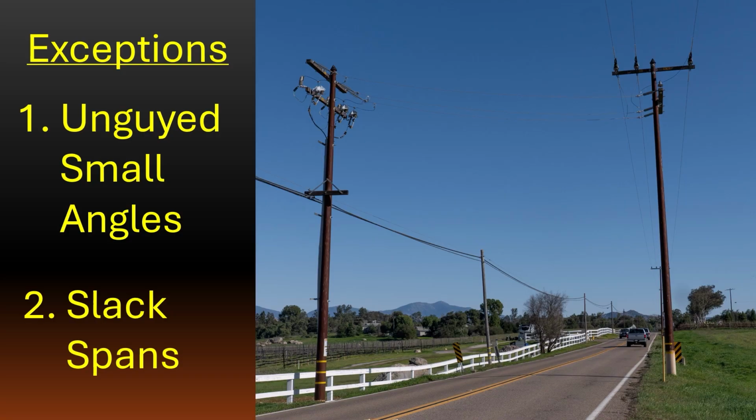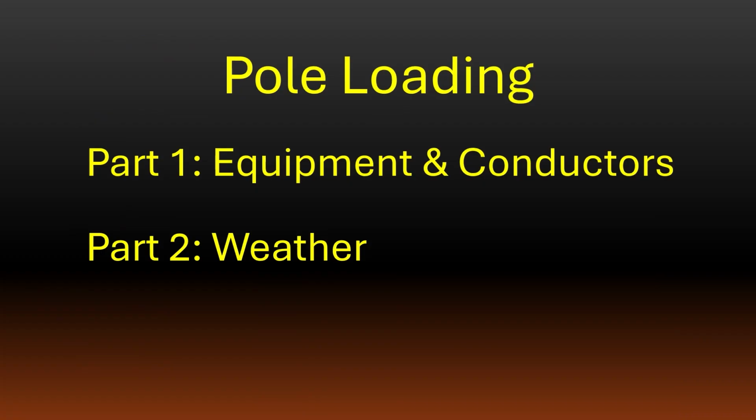A closer look at the pole on the right will show that it's beginning to lean to the left as a result of the slack span. Stay tuned for part 2, where we talk about the additional loads on poles due to weather.